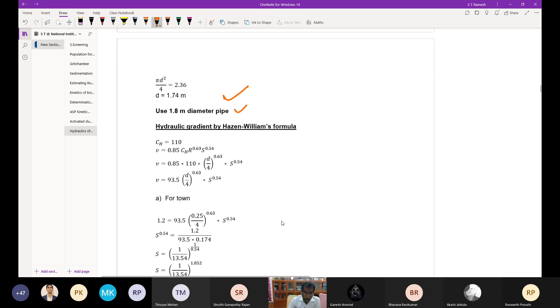Yes. Now we have to find the slope, because the diameter has been found. We have to find the slope of the pipe to be laid. For that you can use the Hazen-Williams formula, and you can refer to the tabular column we saw in the slide. Based on your pipe, pick up the CH value from the table and write down the formula directly. You can substitute 1.2 meter per second as the velocity, because we assumed it, and R is equal to d by 4.